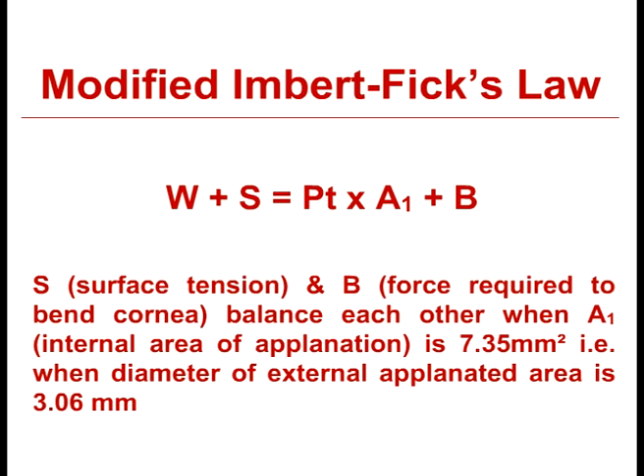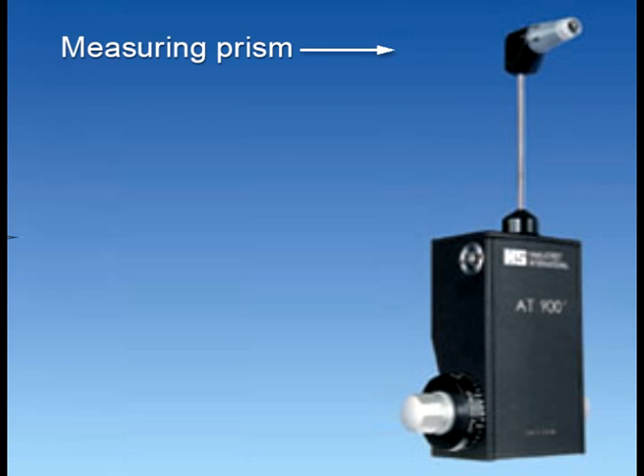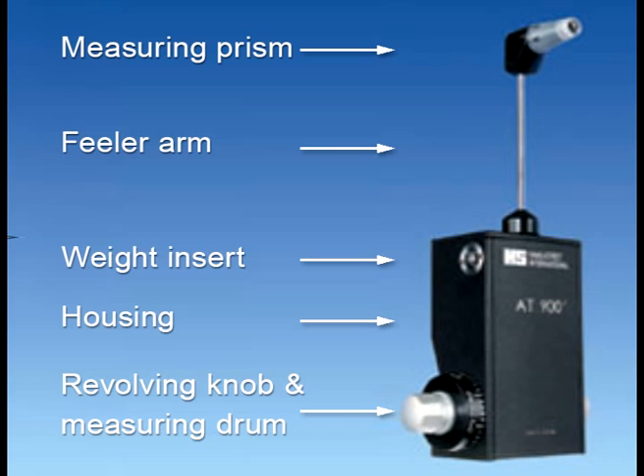At this stage, the law becomes applicable. The Goldmann applanation tonometer consists of 5 parts: the measuring prism, feeler arm, control weight insert, housing, and revolving knob with measuring drum. Different models are available for different types of slit lamps.